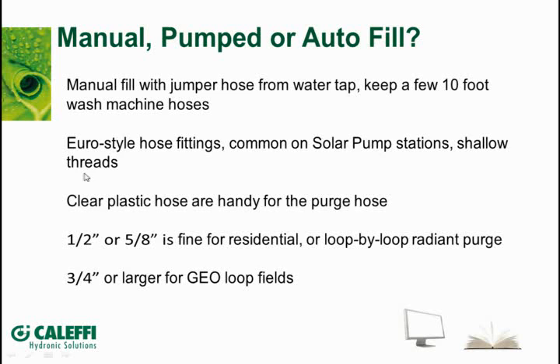One thing I'll caution you about, if you're doing any solar work, a lot of those prepackaged solar pump stations will have a European-style hose fitting on them. It looks a lot like a standard garden hose thread, but it's a little bit shallower, and a regular garden hose fitting, as we know, doesn't always seal on those. Sometimes you can cheat them a little bit and put 2 gaskets in there and they'll tighten up, but it's a shallower socket that they're having their hose fitting, so it can be a little tough to seal that up.